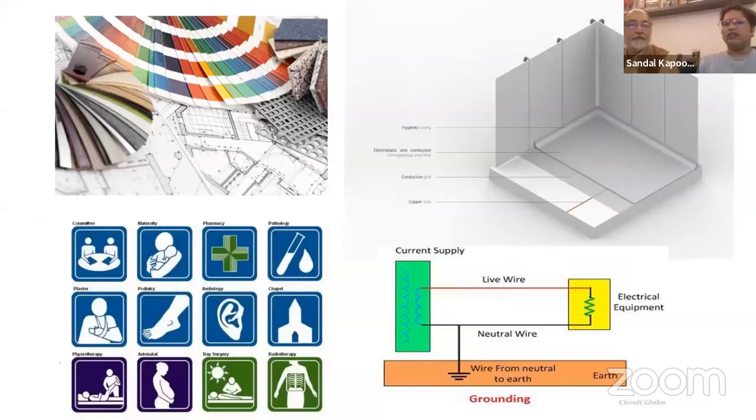Another consideration is about the materials that we are going to use, and about the signages, because in the radiation protection zones, wherein we have the heavy, radiation-prone equipment, those signages and warning signs have to be placed. Yes, it's very, very important that the operation theaters and others have conductive flooring. We have it all inbuilt in the materials we get, but it's very important to do independent earthing and grounding very properly.